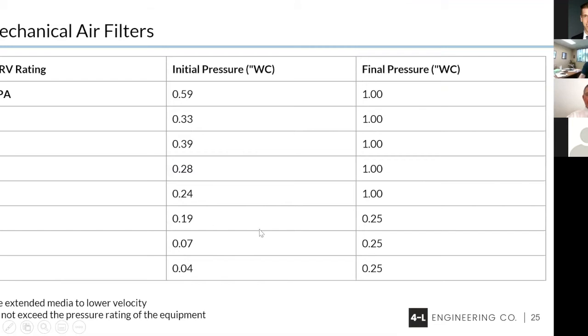Here's what I'm talking about, the resistance of the filter. If you look, if I have a MERV 1 filter there at the bottom of the chart, the initial pressure drop is around 0.04. When I get to 0.25, that is the final pressure drop, and that filter is done. It's loaded. The problem is some of the fans that we use only have the capability of producing around 0.3 external static. So somewhere before I reach that full loading, that filter will have to be changed.